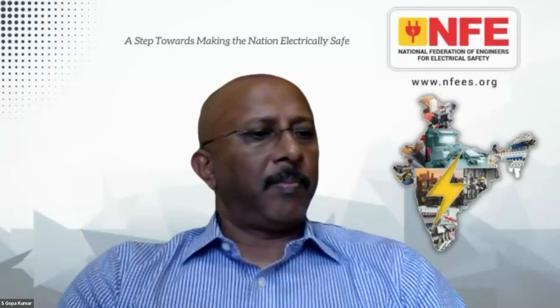See, as Gopa said, we should not design absolute impedance for the probable fault level, say 30 kA or 50 kA. The current that will be seen by the circuit will be in the order of 4 to 5 kA after allowing for the various sensing devices. Say you have a CT, you have a setting for the time multiplier, everything is there. Finally, what the standard says is the permissible touch voltage and the permissible duration. That is achieved in simple terms.